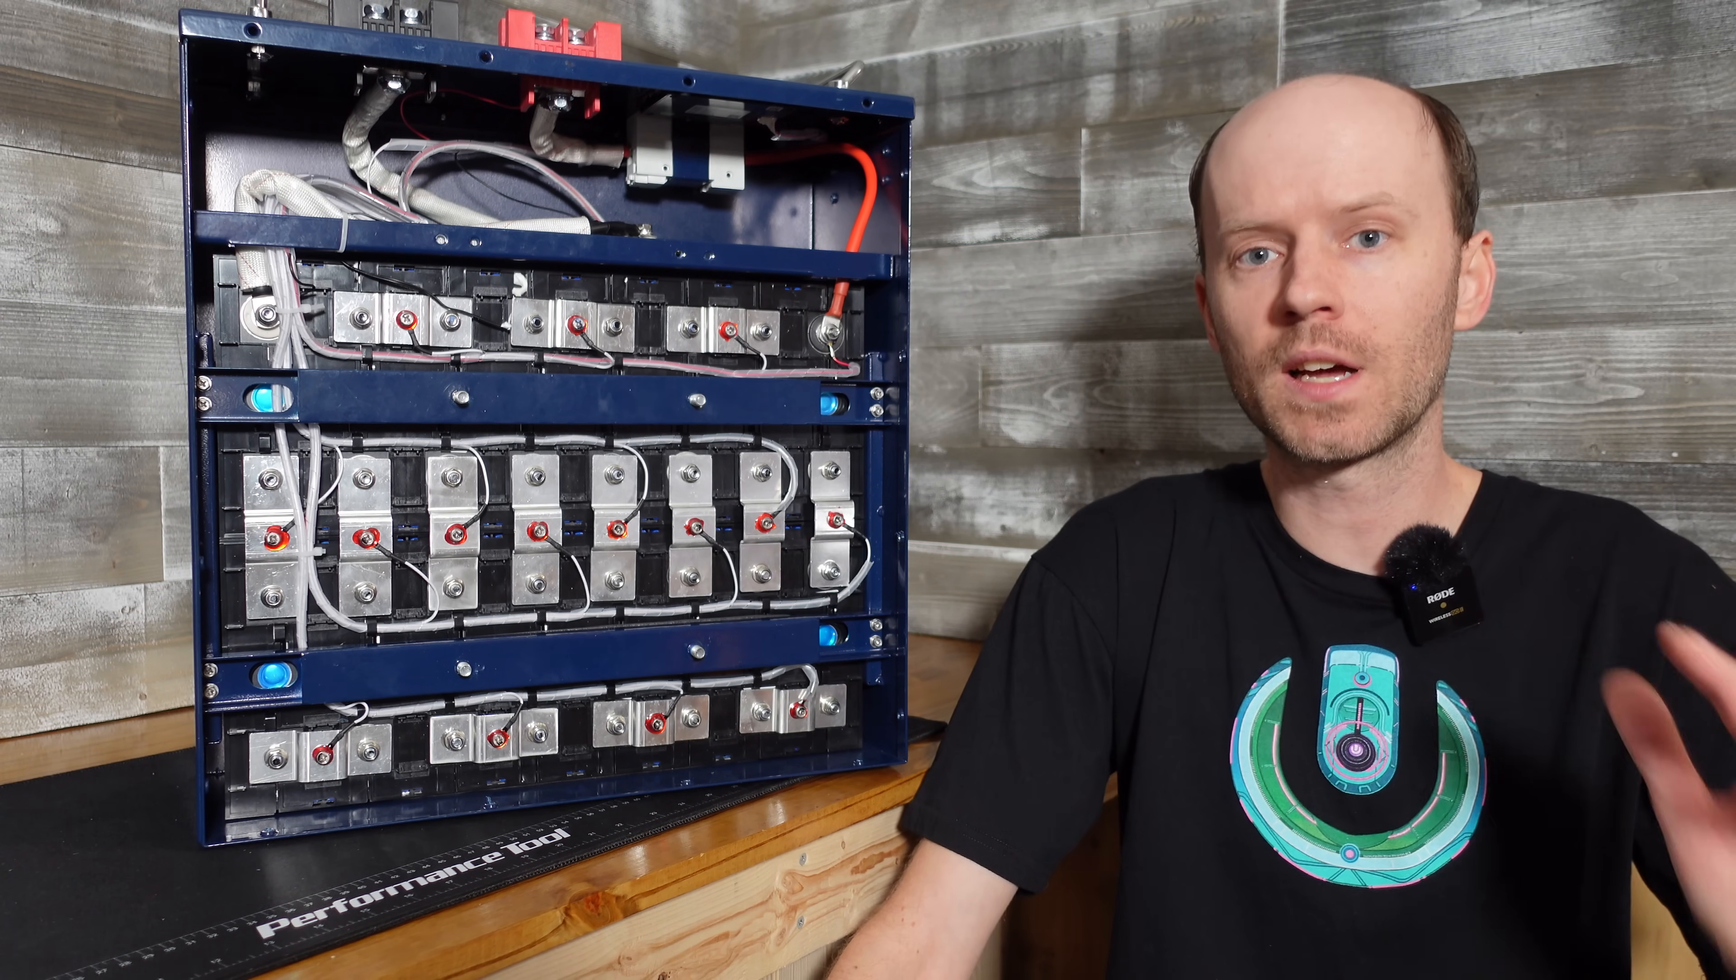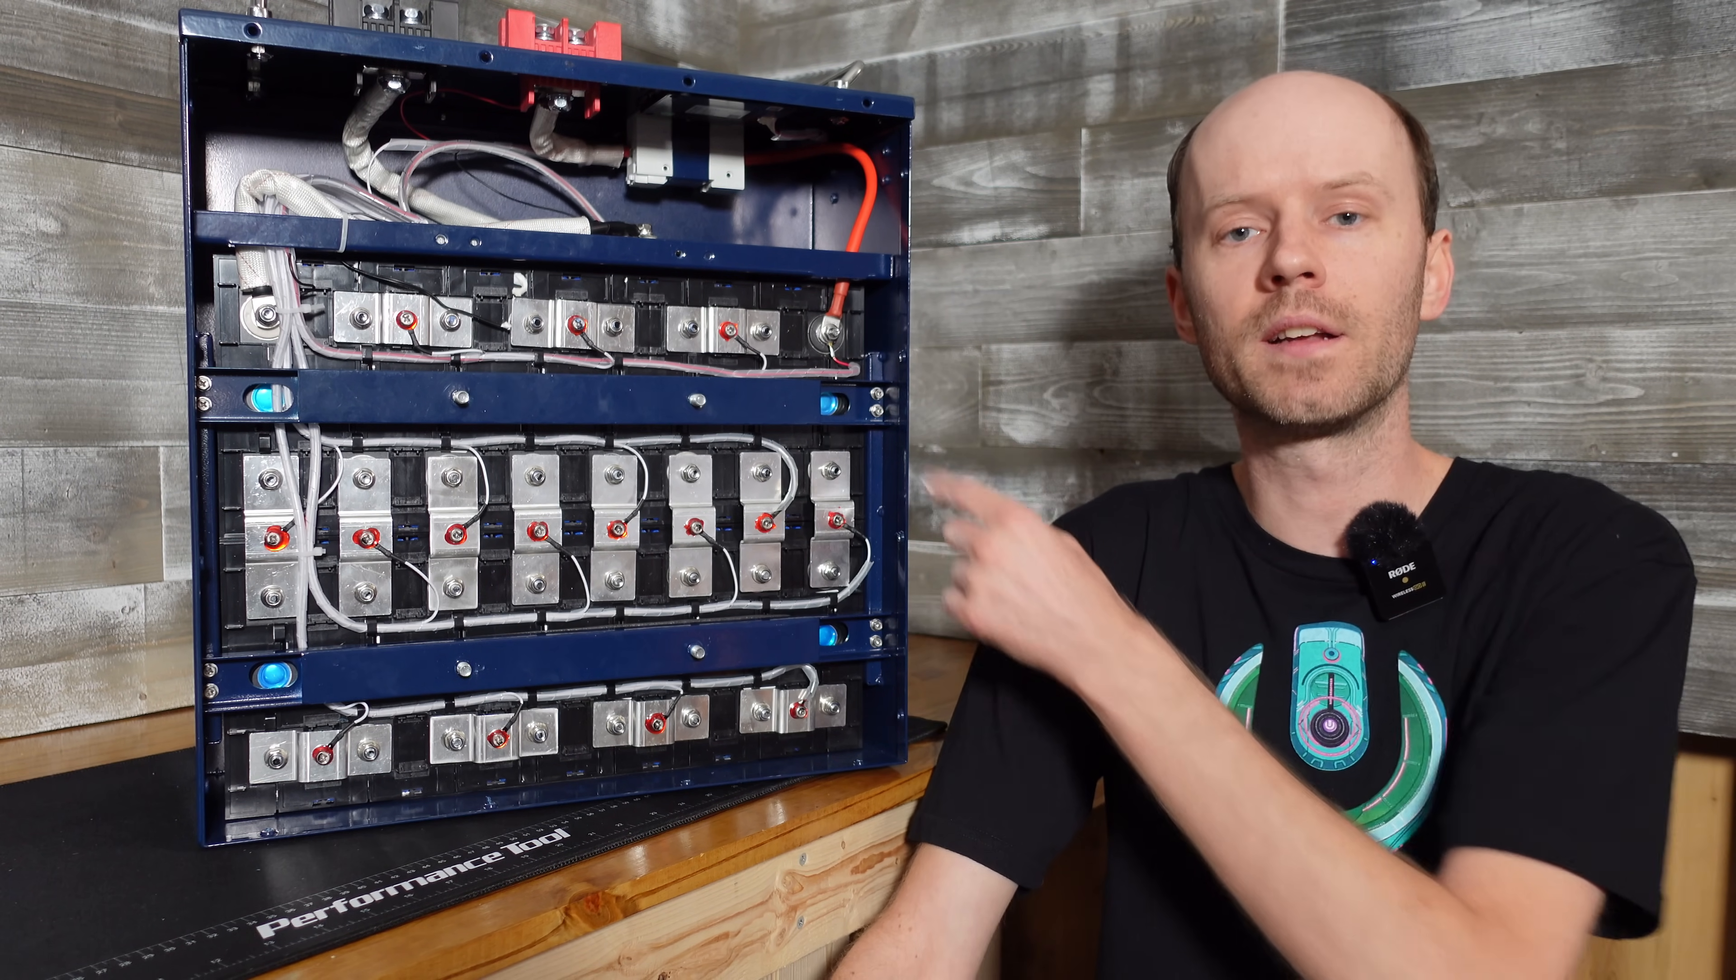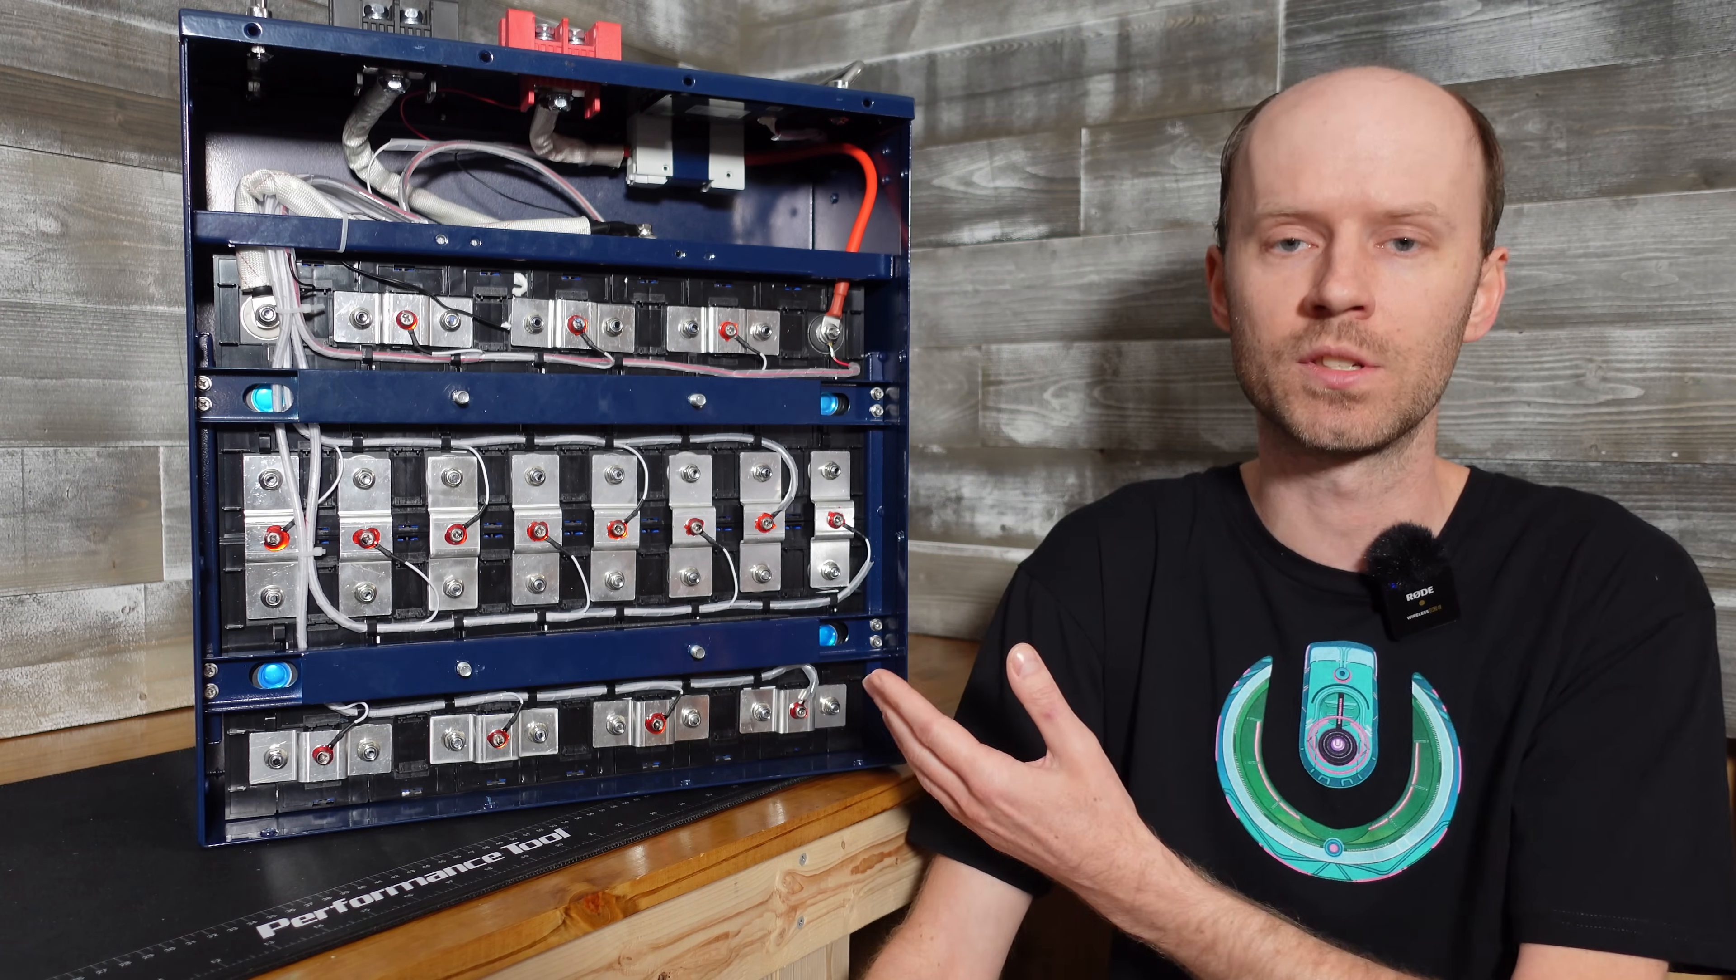Fortunately, while I did have to cut that nut off and I did damage a number of the threads in the process, there were still enough threads left that I was able to put a new nut on, as you can see right here. And that allowed me to run the capacity test. Now I am still going to replace the cell because my philosophy is always when in doubt, throw it out, right? The cell's damaged. Well, the cell's not damaged. The terminal's damaged.